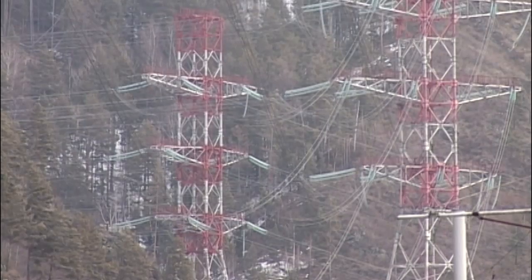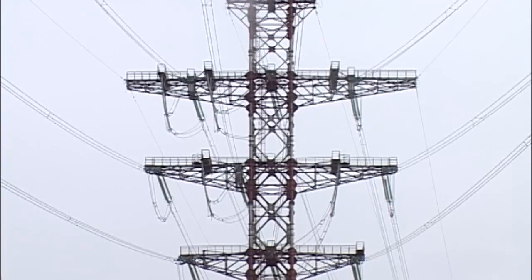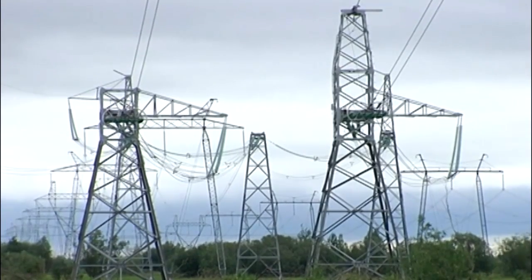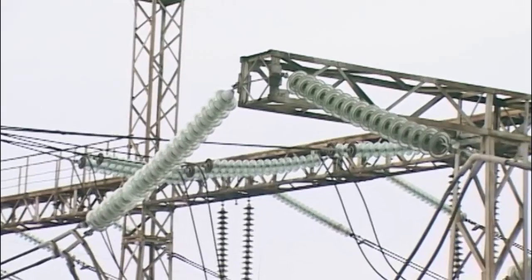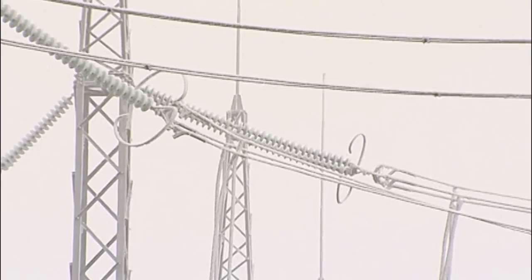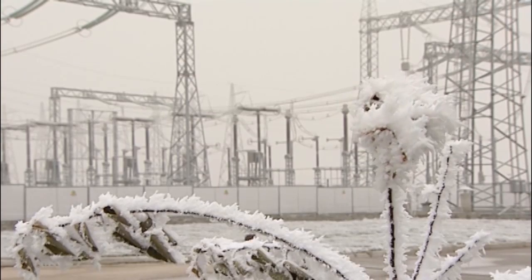In 1978, the second stage of substation 500 kV Magnitogorsk was put into operation with the 500 kV high-voltage line Troitskaya Hydroelectric Power Station–Magnitogorsk, with the capacity of 1,362 MVA on station. In 1976, despite conditions of industrial pollution on the 500 kV line Iryklinskaya–Magnitogorsk, the insulator of type PS-12A with the standard profile was used.